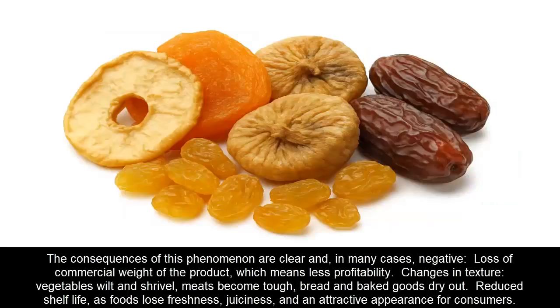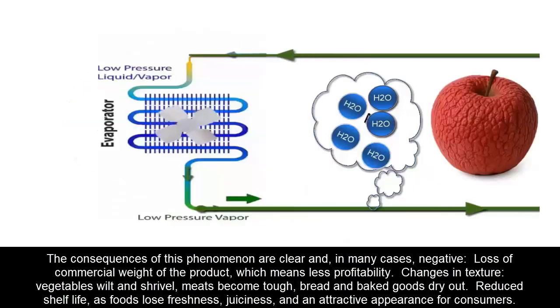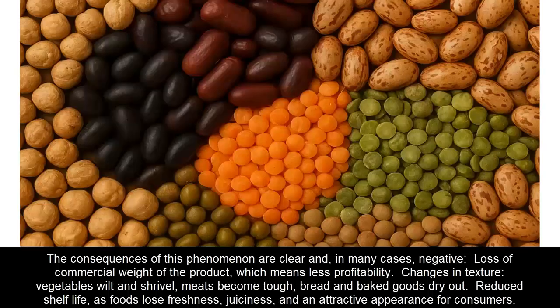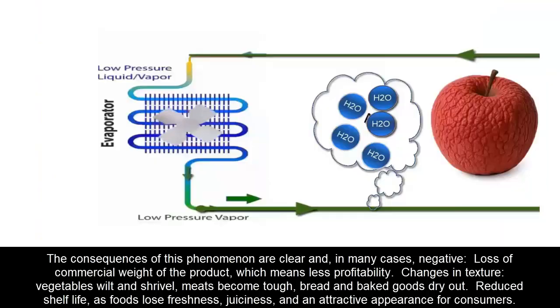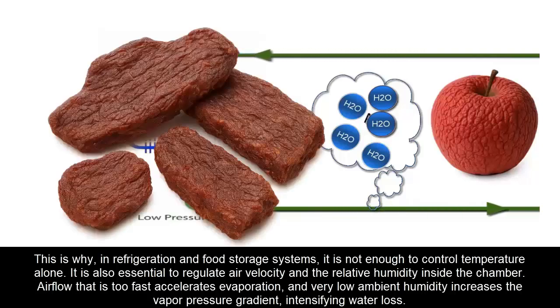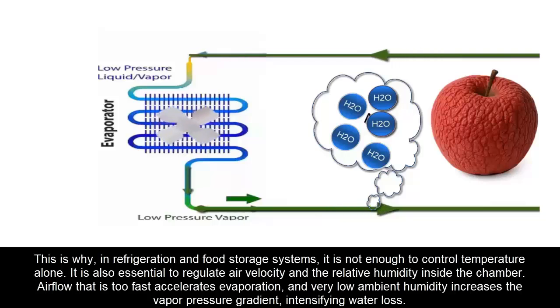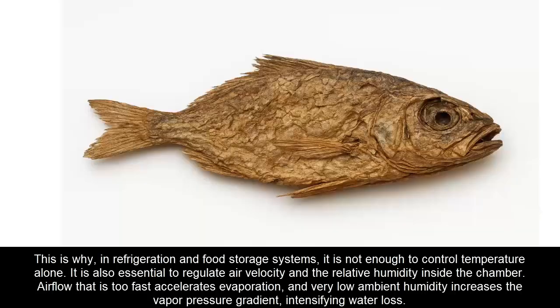Changes in texture: vegetables wilt and shrivel, meats become tough, and bread and baked goods dry out. Reduced shelf life as foods lose freshness, juiciness, and an attractive appearance for consumers. This is why in refrigeration and food storage systems, it is not enough to control temperature alone. It is also essential to regulate air velocity and the relative humidity inside the chamber.